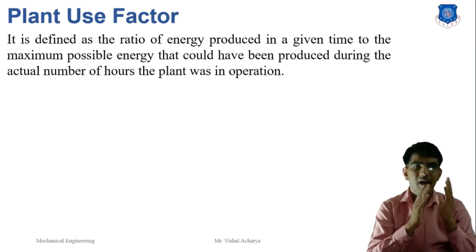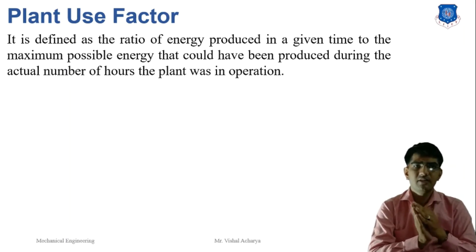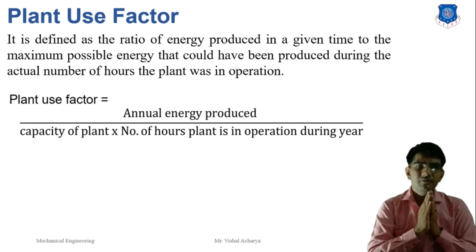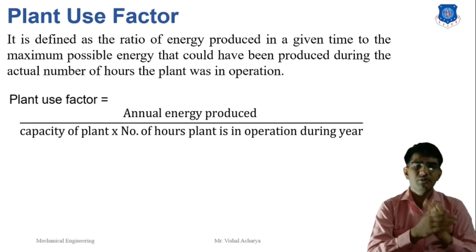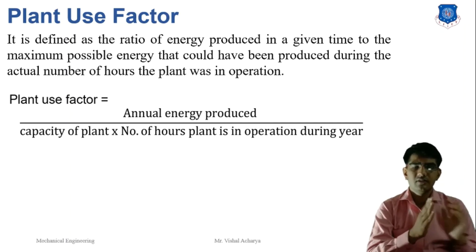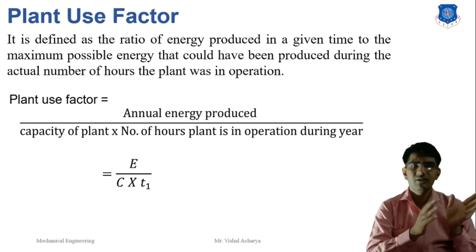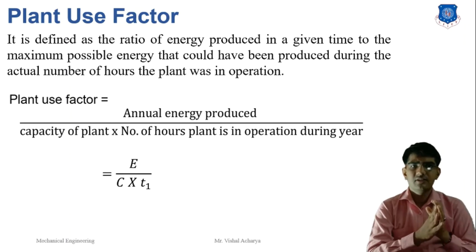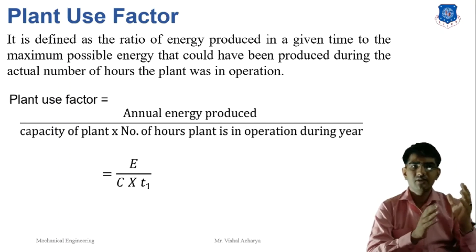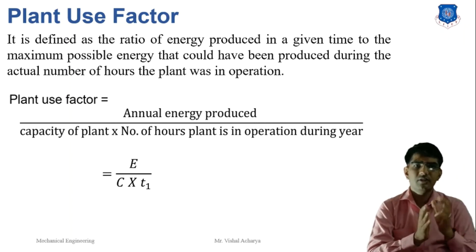The next term is the plant use factor. It is defined as the ratio of the energy produced in a given time to the maximum possible energy that could have been produced during the actual number of hours the plant was in operation. Plant use factor = annual energy produced (E) / (plant capacity (C) × number of hours plant operated during the year (T)). For example, if total energy produced is 10,000, plant capacity is 20, and hours of operation are 1000, then plant use factor = 10,000 / (20 × 1000) = 0.5.